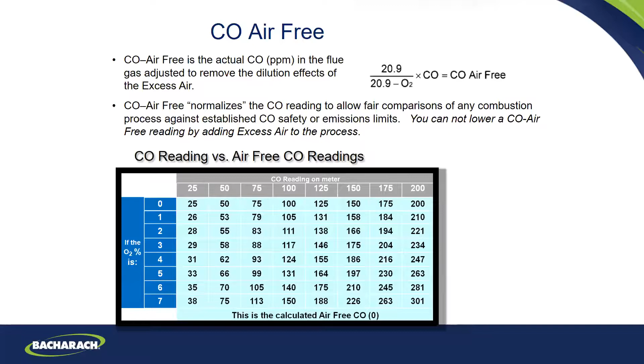So you need to know which code you're working at. A lot of times, AGA says you're allowed 400 parts per million CO air-free. Well, I would never set up a furnace in a house at 400 ppm regular CO. That's extremely dangerous. Usually that code is like 100. So you want to make sure whether the code is CO air-free or just raw CO, and then you comply with it by looking at the right CO reading.